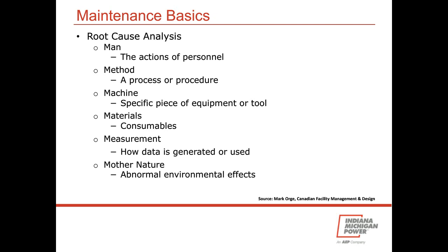The materials category might include clogged filters or adding polyolester refrigerant oil that clogs heat exchangers. The measurements category might be a building automation system deficiency or a spurious signal coming from a sensor, maybe trusting that dampers are shut when they're not, which we talked about. And the Mother Nature category could be excess humidity or rain, for instance, that's causing this unusual maintenance condition. So just some things to think about when you're trying to diagnose your maintenance issues.